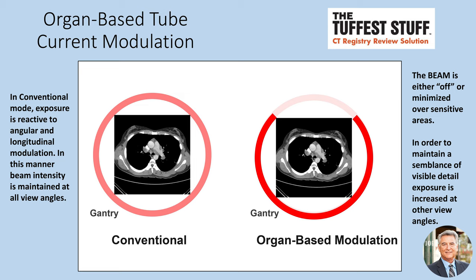When we look at organ-based tube current modulation, the beam is either off or very much minimized over sensitive areas. In order to maintain a semblance of visible detail, beam intensity and therefore exposure has to be increased at other view angles. That's why the diagram shows a darker red in the area where exposure is taking place, while over the anterior surface — the sensitive areas — there is either no exposure or very little exposure.